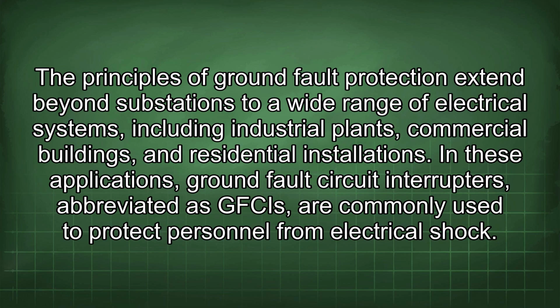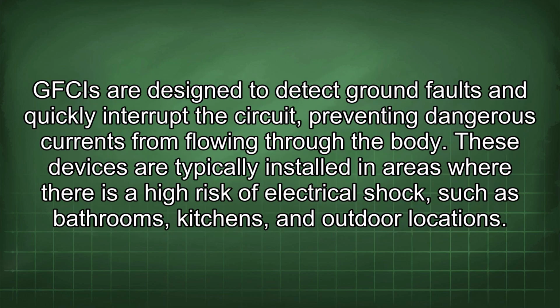The principles of ground fault protection extend beyond substations to a wide range of electrical systems, including industrial plants, commercial buildings, and residential installations. In these applications, ground fault circuit interrupters, abbreviated as GFCIs, are commonly used to protect personnel from electrical shock. GFCIs are designed to detect ground faults and quickly interrupt the circuit, preventing dangerous currents from flowing through the body. These devices are typically installed in areas where there is a high risk of electrical shock, such as bathrooms, kitchens, and outdoor locations.